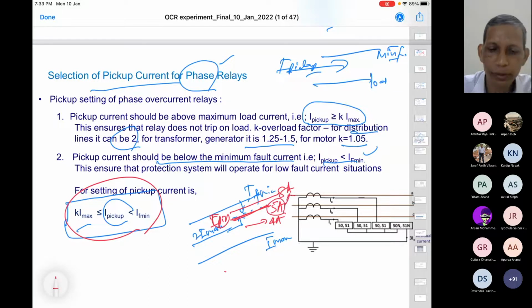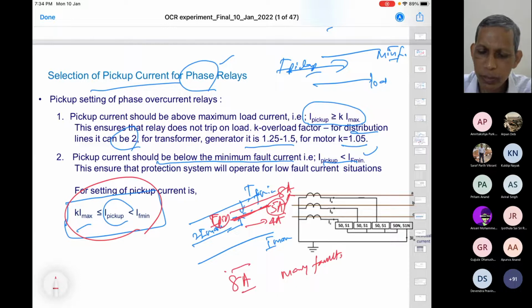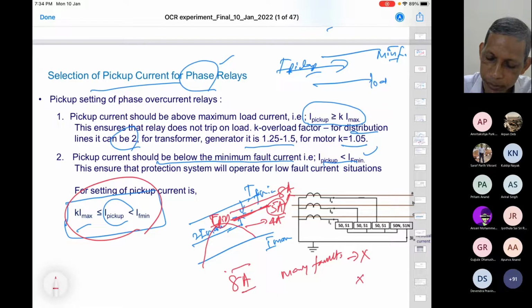If I go for 8 ampere, what does it mean? It means that many faults, which have some resistance in the path or arcing and so on, cannot be identified. But you see here, if it happens to be 8 ampere, even if the load grows momentarily to a higher level, it will not trip. Good thing. So this is a good thing. But when the fault happens to be there with some resistance and it could not discriminate, then this is not a good thing also.